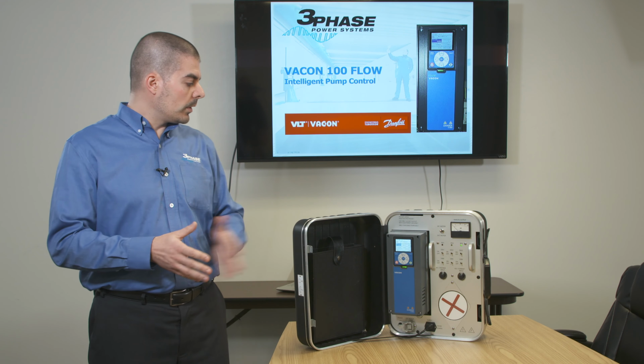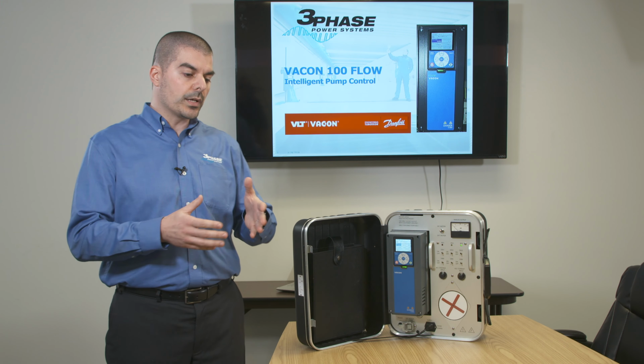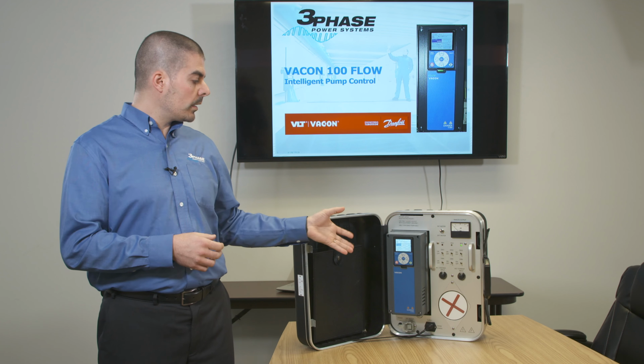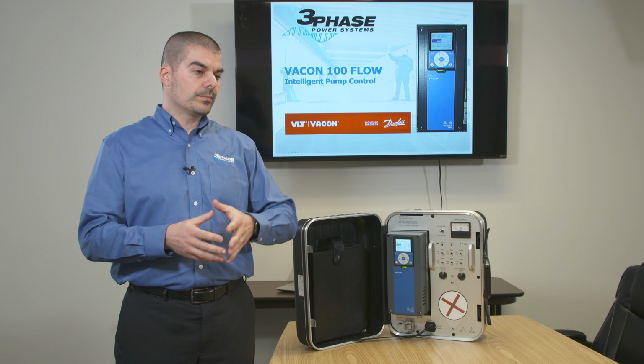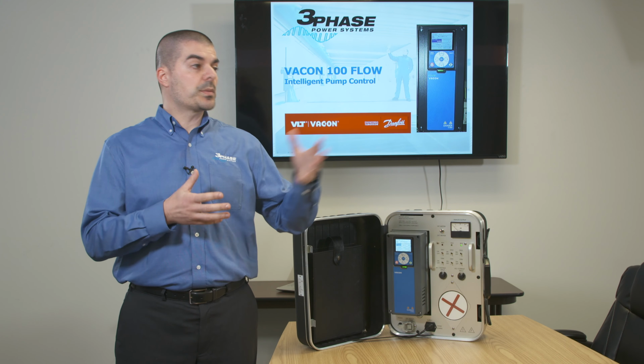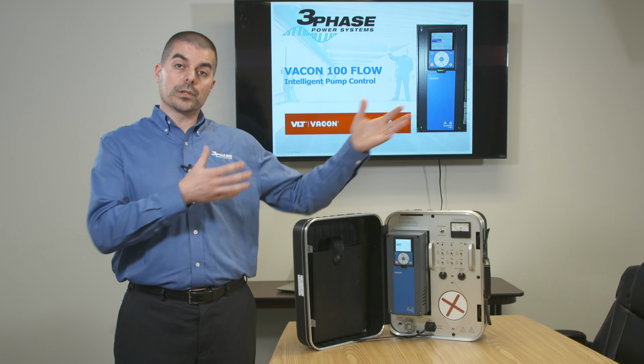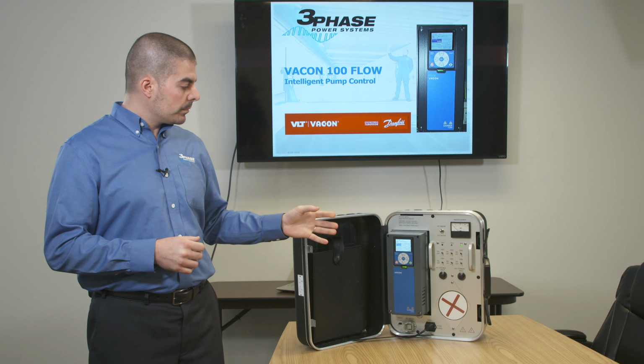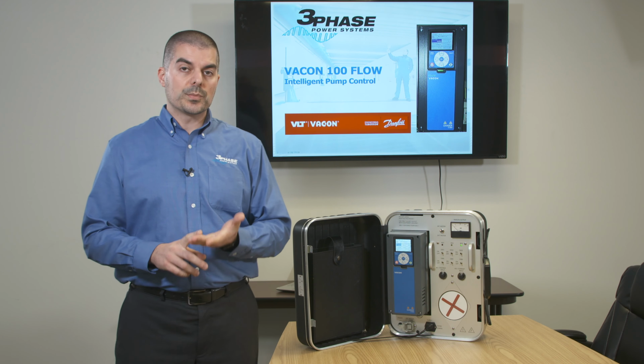So how Danfoss addressed this is by replacing the electrolytic capacitors of traditional drives with thin film capacitors. We can leave these drives in storage as a spare on a shelf for years, and the capacitors will never dry out. And the lifespan of these capacitors is up to 10 times as long as electrolytic capacitors. Now, this is the first issue that is being addressed.